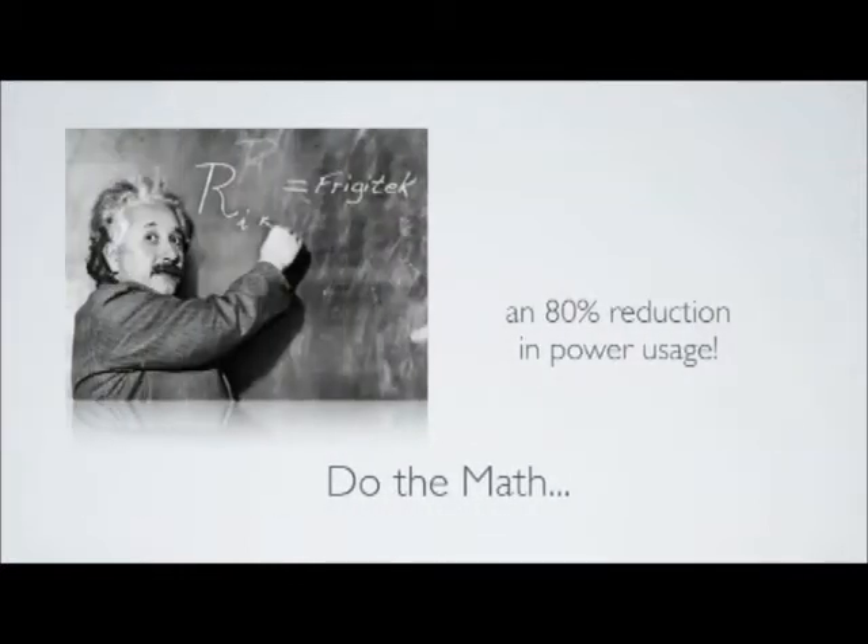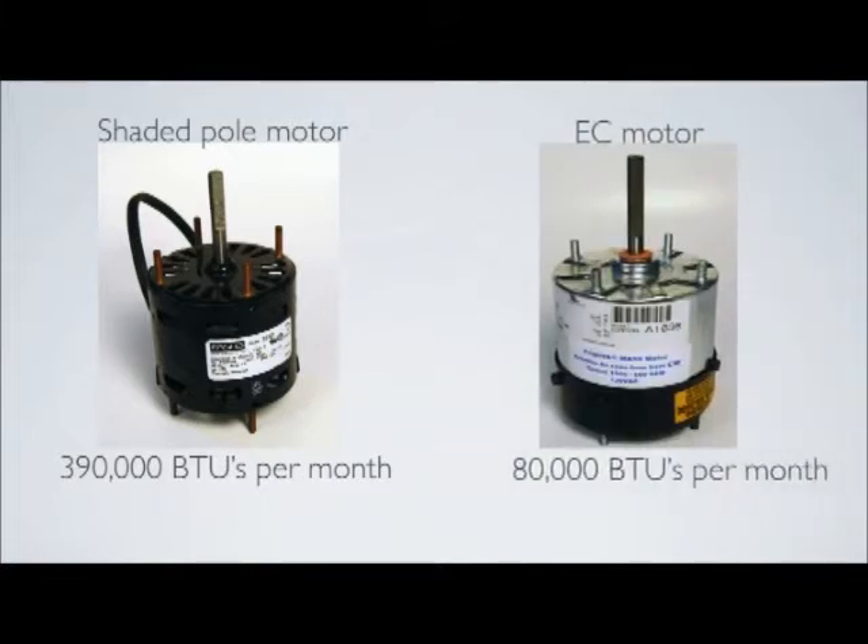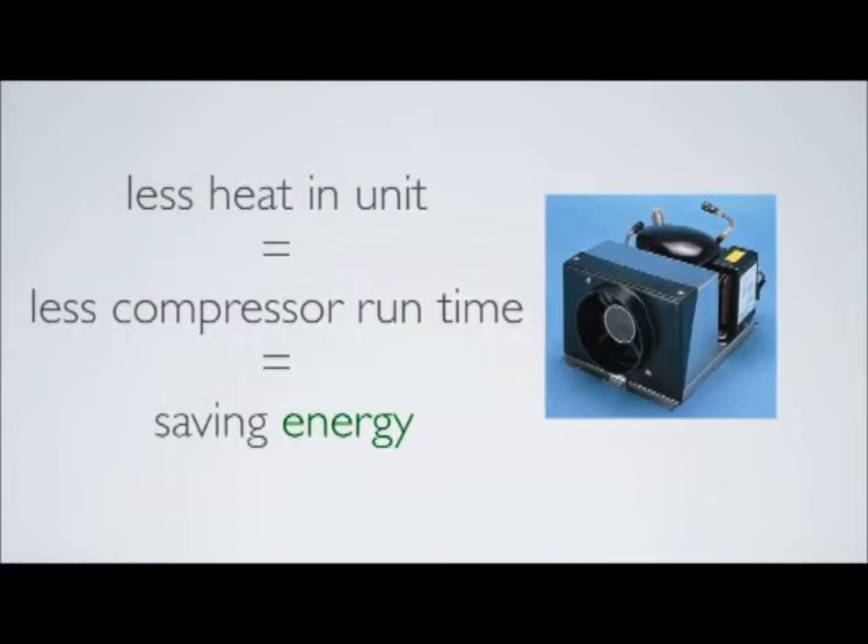When you do the math, this amounts to about an 80% reduction in power usage. Along with this comes a significant reduction in heat created in the box. The standard shaded pole motor will generate about 390,000 BTUs of heat per month, while the 2-speed EC motor with the Frigitek controller will generate less than 80,000 BTUs per month. With less heat being released in the unit, compressor run time will be reduced — again, saving energy.